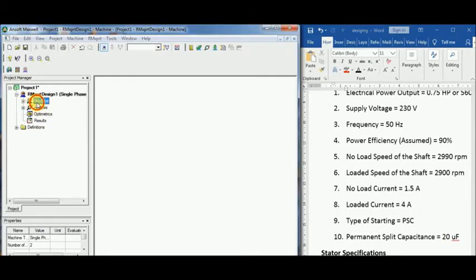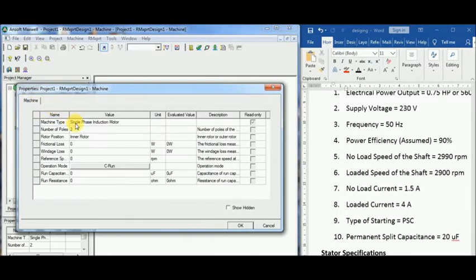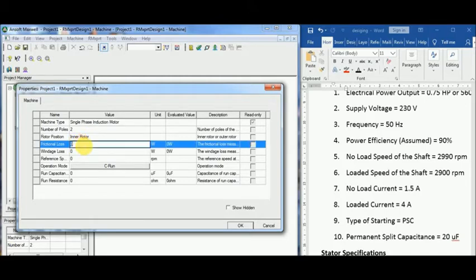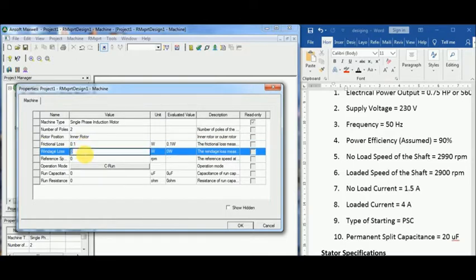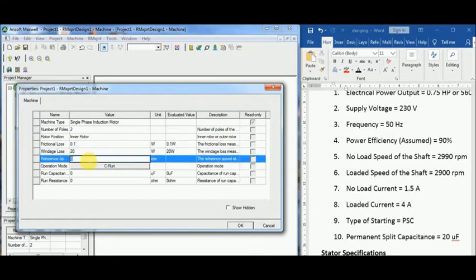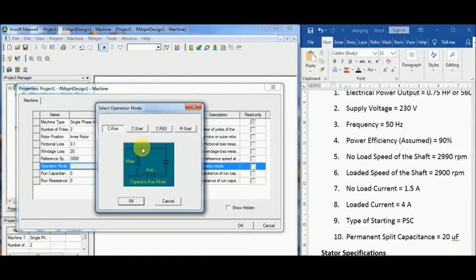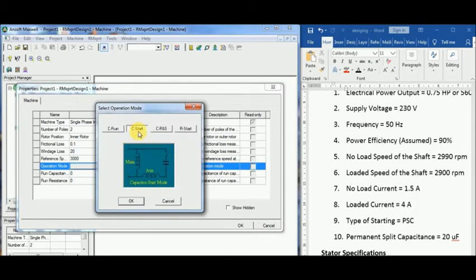Under the machine, since this is a single phase induction motor, I'm going to leave this at two poles. Rotor type is cage. Since the rotor is connected through the bore of the stator, friction losses assumed to be 0.1 watts, but the windage loss I'm assuming is 20 watts. These measurements we have been observing since a very long time in our production cycle, so we know roughly this amount would be lost. But if there were some special conditions such as damaged bearings and higher friction, the loss would be extremely high.